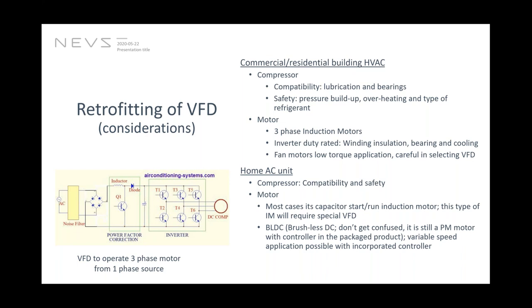Now, I would like to mention a disclaimer here. BLDC is not a DC motor. It's a permanent magnet motor with a controller in the package product and can be directly connected to a DC supply. So basically, it's a three-phase permanent magnet motor with a controller included. You can directly plug it into the DC. The figure on the bottom left corner shows such an application of the VFD in BLDC motors. If you have a BLDC in your home AC unit, then it's probably that variable speed has already been implemented, so it doesn't make any sense to retrofit the VFD. So these were the considerations that I had when looking into the retrofitting of old systems.